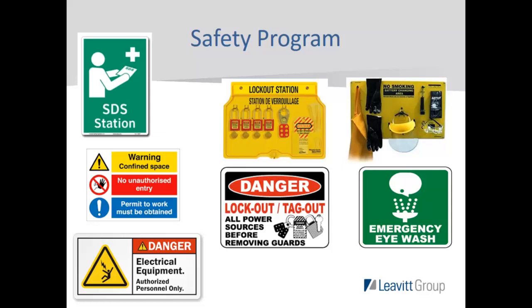I need to highlight the importance of having a lockout tagout procedure specific to the equipment. That's a common mistake I see in a lot of facilities - they do have a general lockout tagout program, however they do not have a procedure on how that particular piece of equipment needs to be de-energized. So that information needs to be written out, probably by your in-house safety team and/or maintenance, and needs to be available at the lockout tagout station or available to your maintenance team and your authorized staff that are going to be performing the procedure.